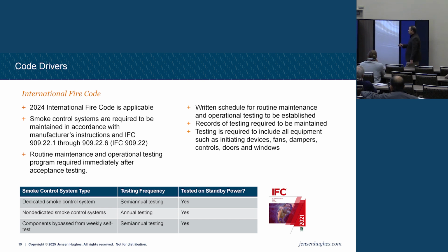All right, so when we start looking at it, there's dedicated, non-dedicated, and then components that are bypassed on weekly self-test. We'll talk dedicated and non-dedicated a little more as the presentation goes on, but it's kind of self-explanatory. If it's equipment that is only there for smoke control, stair pressurization, right? It probably doesn't do anything else in your building except pressurize that stairwell. That would be dedicated equipment, and I'm testing that semi-annually, okay? Non-dedicated smoke control equipment, I'm testing annually. Why can I test it less frequently? It's also got a normal job. So if that air handler fails, I know that air handler failed because everybody's complaining it's now hot on the 7th floor, right? So that's why for non-dedicated, the frequency is a little different.